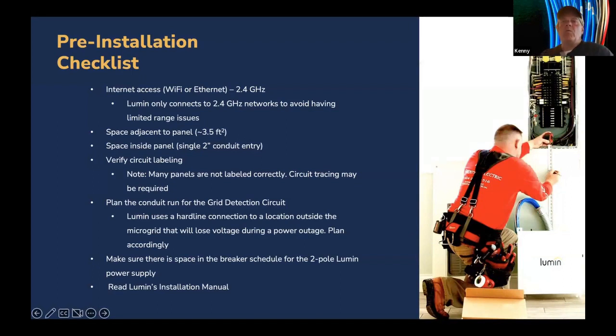We also want to make sure that we have 2.4 gigahertz available on site. And the Lumin Smart Panel, being pre-wired, needs about 3.5 feet of space adjacent to the panel so we don't have to do any extensions, though you could do extensions. We do have a 2-inch conduit with the pre-wired whip. The conduit itself is about 22 inches with about 5 feet of lead. So for pretty much any current service panel, you won't have to do any extensions.